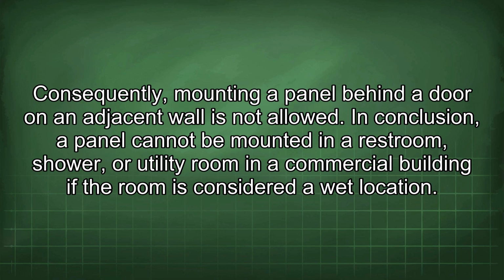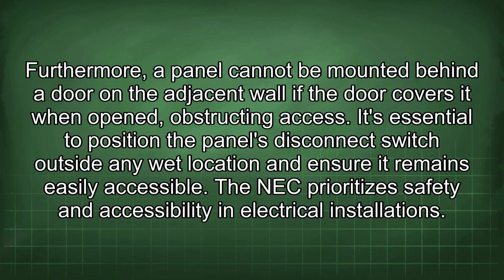In conclusion, a panel cannot be mounted in a restroom, shower, or utility room in a commercial building if the room is considered a wet location. Furthermore, a panel cannot be mounted behind a door on the adjacent wall if the door covers it when opened, obstructing access. It's essential to position the panel's disconnect switch outside any wet location and ensure it remains easily accessible. The NEC prioritizes safety and accessibility in electrical installations.